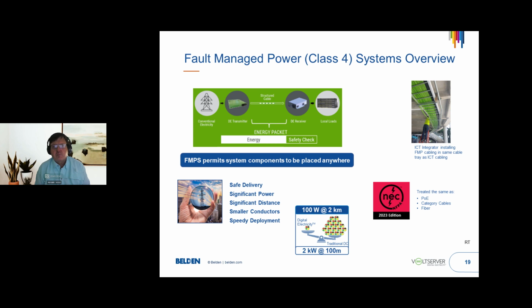So if anybody asks you, what is fault managed power, what's digital electricity, what's class 4, your answer is the 5 S's: safe delivery, significant power over significant distance using smaller conductors, providing speedy deployment. And we've already said with digital electricity, it's a series of pulses that are monitored, and if anything goes wrong between the transmitter and receiver, it instantly turns off and prevents anything bad from happening from some type of fault.